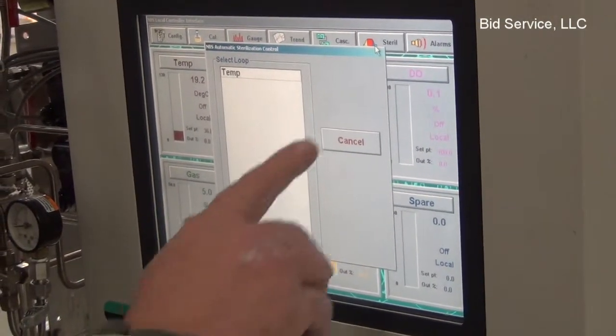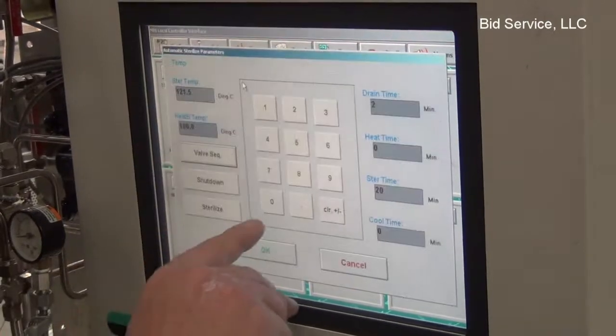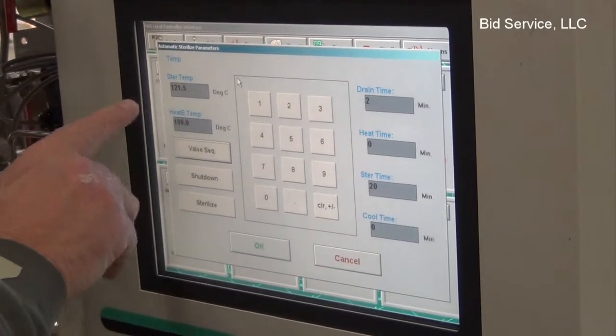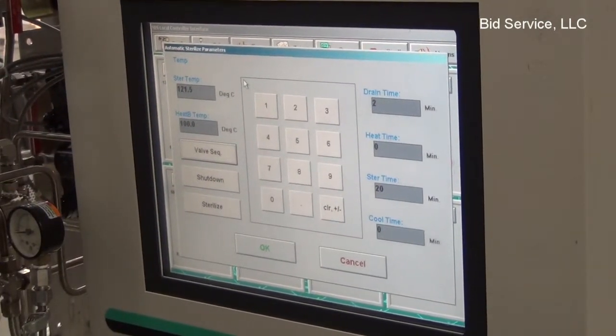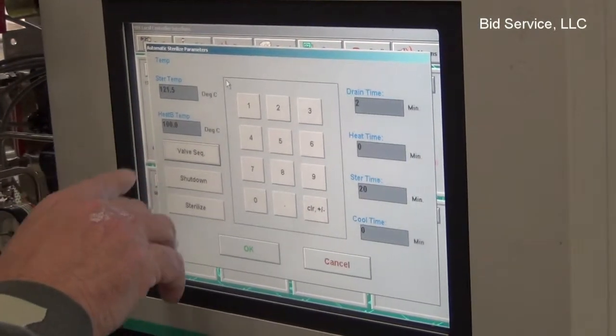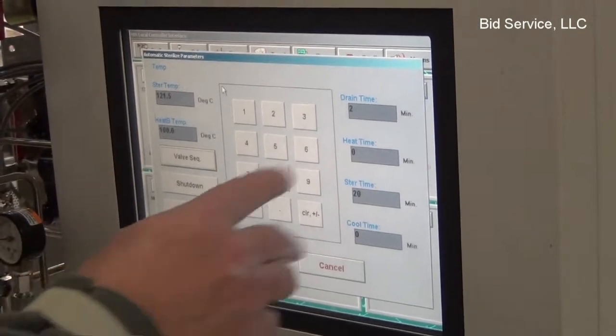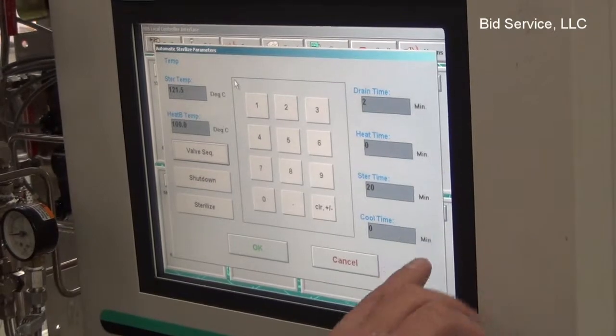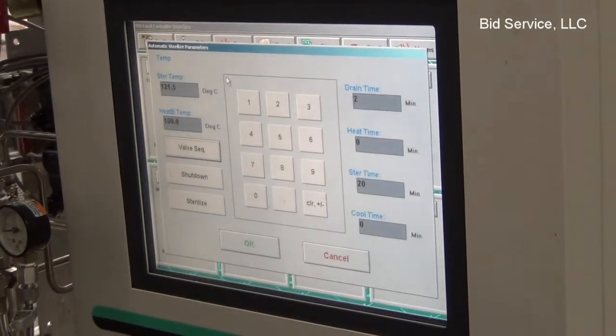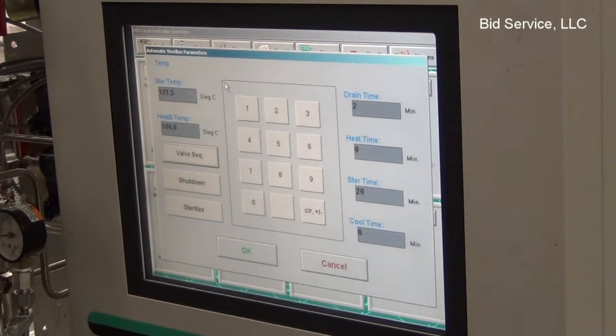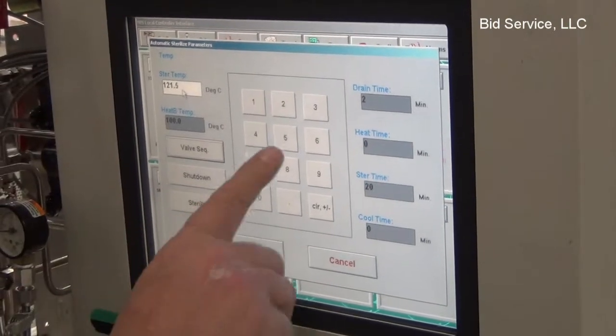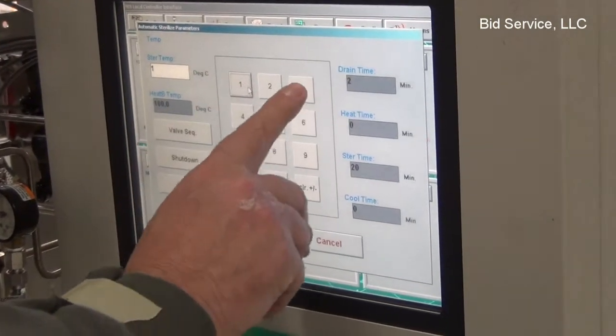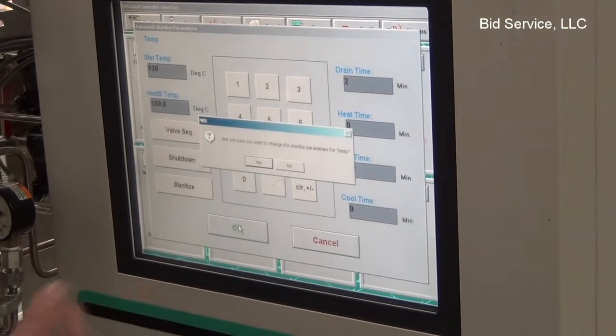This is your sterilization loop. You go in, select temp. Here, this is for your steam connections. You would have your sterilization temp, your heater temp, your drain time, heat time, sterilization time, and cool time. These are all parameters that are user configurable. You just go in, hit the button, change it to what you wanted, and say OK.